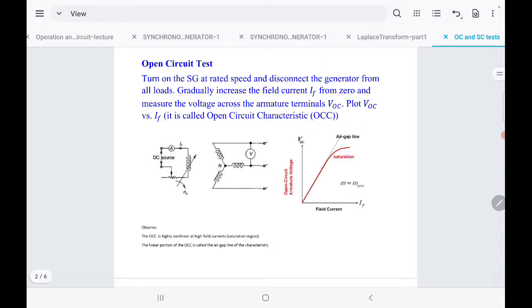The first test is the open circuit test. We have a synchronous generator in the lab and we change the variable resistance in the field circuit to control the field current IF. By controlling IF we control the voltage induced in the stator winding. A voltmeter is connected between two lines to measure the line-to-line voltage. The terminals A, B, C are open, meaning the armature current in any line equals zero.